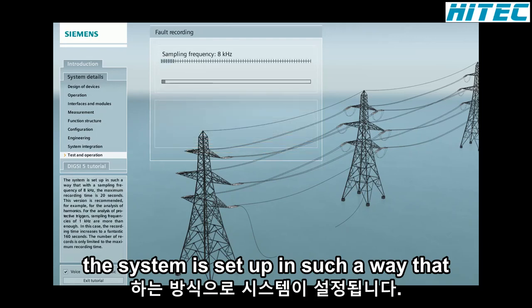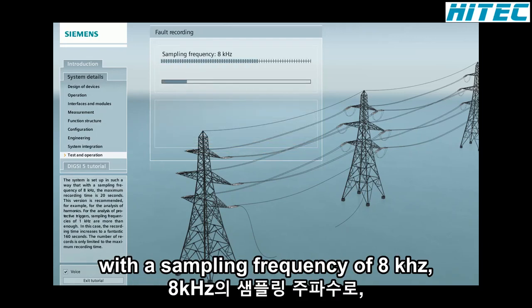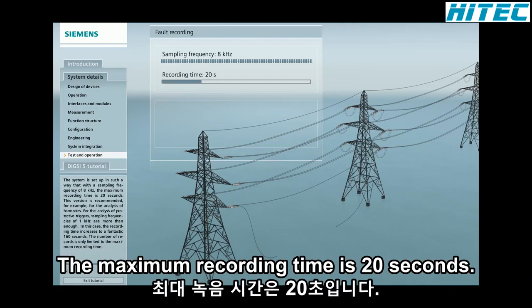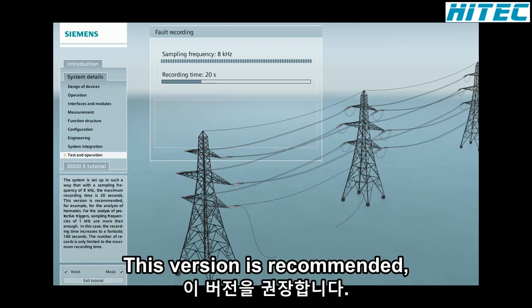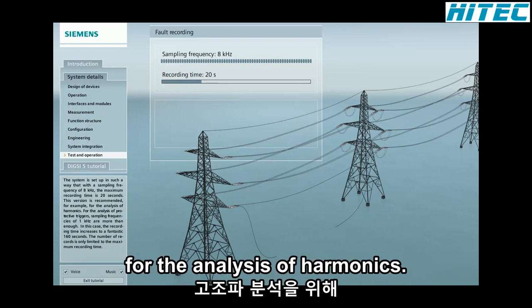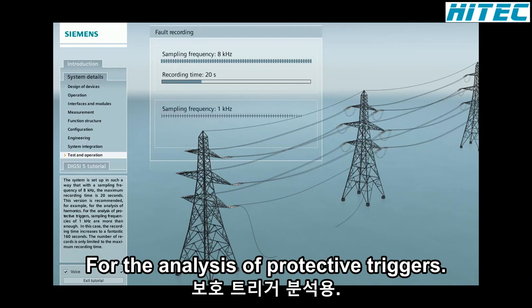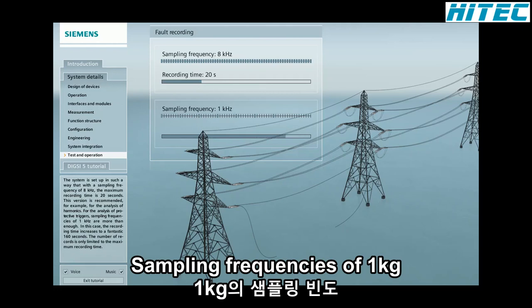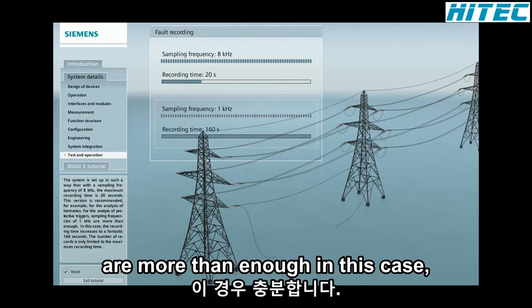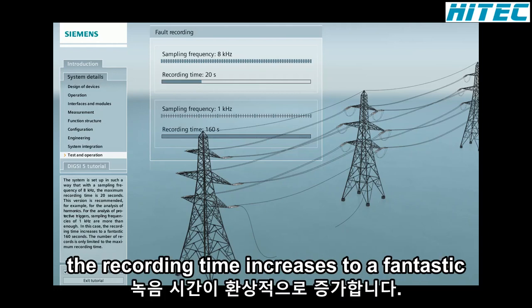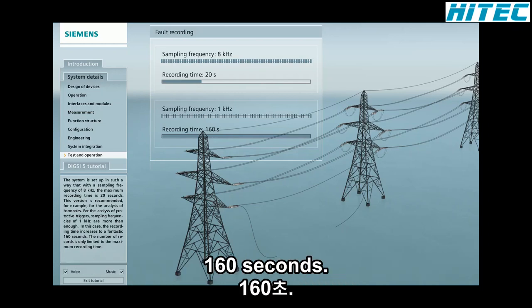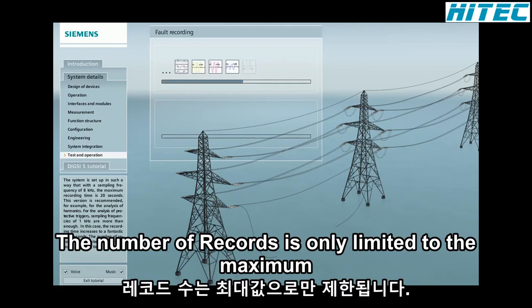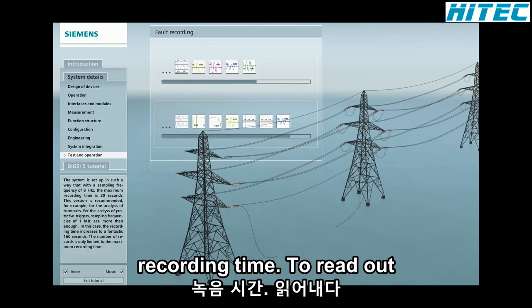The system is set up in such a way that with a sampling frequency of 8 kHz, the maximum recording time is 20 seconds. This version is recommended, for example, for the analysis of harmonics. For the analysis of protective triggers, sampling frequencies of 1 kHz are more than enough. In this case, the recording time increases to a fantastic 160 seconds. The number of records is only limited by the maximum recording time.